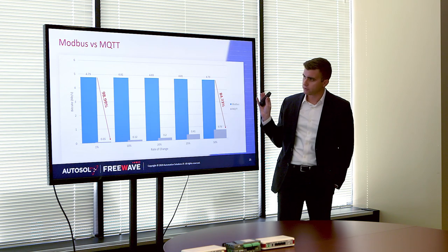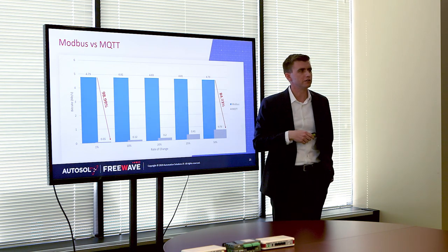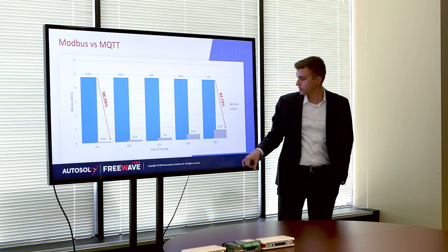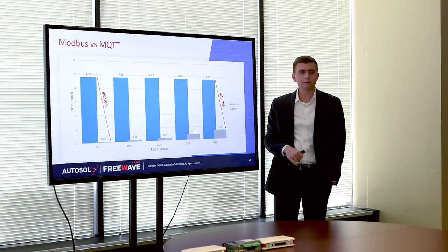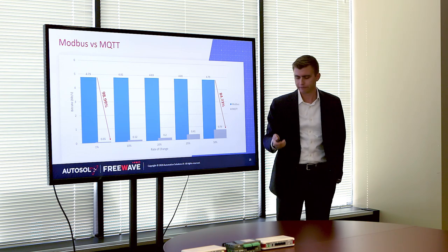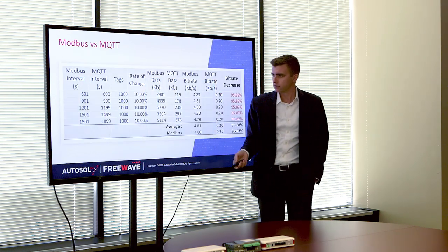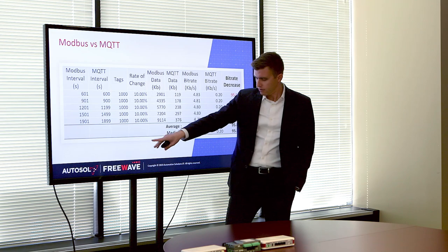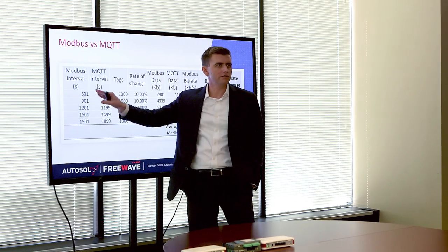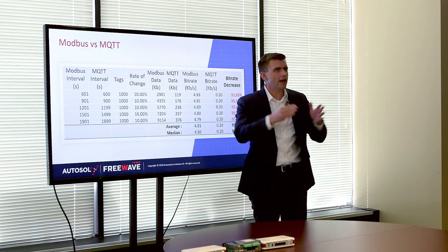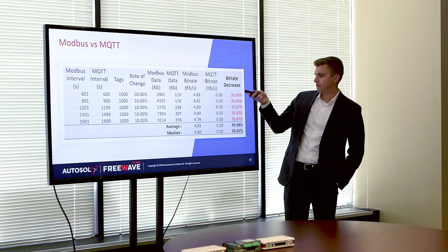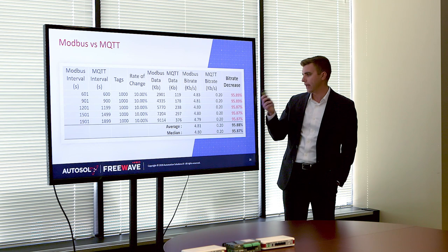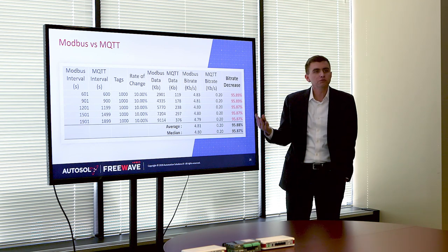On a bar graph, the blue is your traditional poll-response in Modbus and the gray is how much bandwidth was consumed via MQTT for bringing back the same data. For Modbus with rate of change held steady at 10% but time interval going from 10 to 30 minutes, we see a standard decrease of bandwidth consumption of 95.8 to 96% reduction across all intervals — which we would expect, because with traditional poll-response every poll occupies the same amount of data regardless.